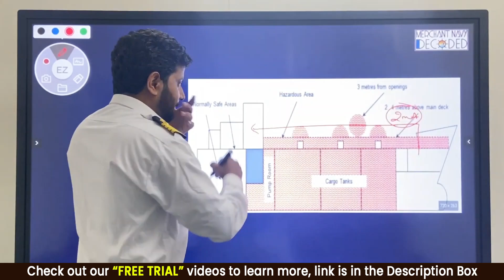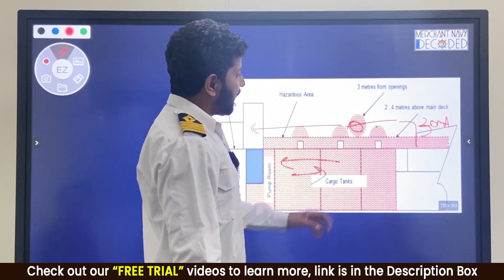Because if it's a 20 milliamp signal coming from here, suppose for some reason over here there's a short circuit in the line and a spark is produced. The spark produced because of a 20 milliamp signal will be so small, it will not have the energy to cause an explosion. But if this is a 30 milliamp signal, and if there is already explosive gas over the tanker, say over here or over there, and there is a spark, then your whole ship is gone, you are gone. This can be the case. So that is why 4 milliamps for stability, 20 milliamps for safety.